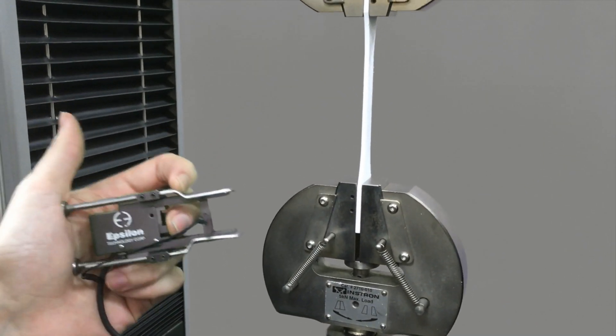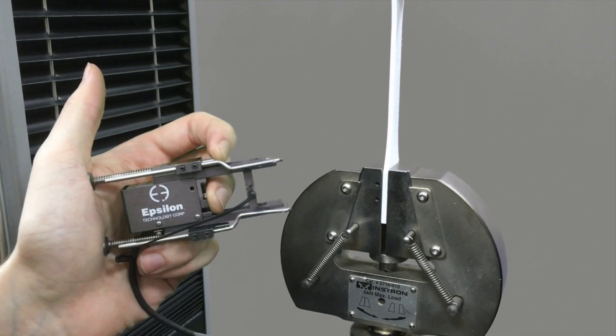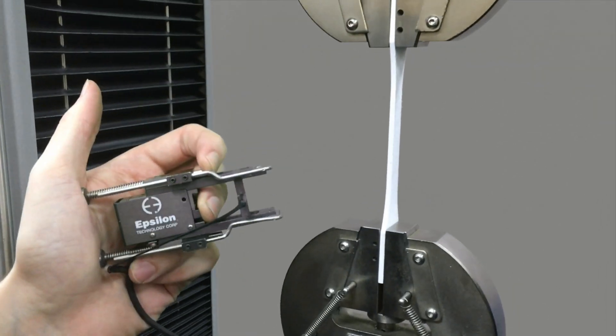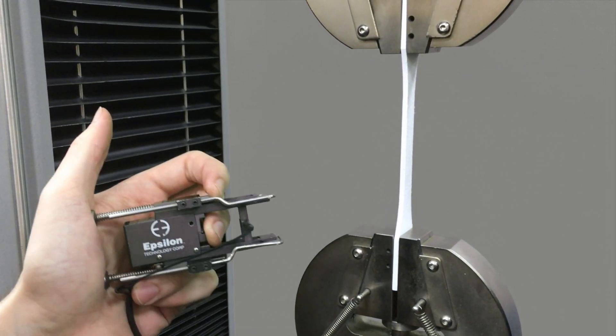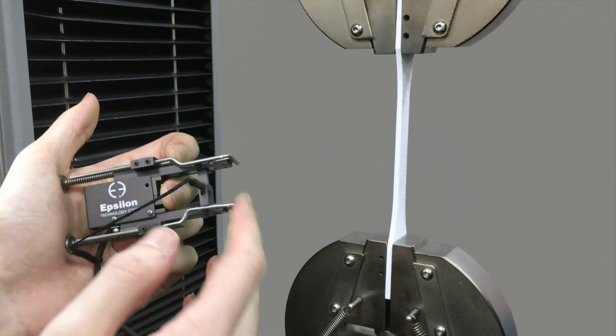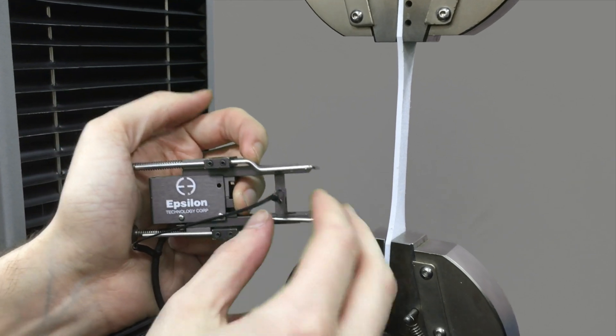The most important thing to remember about extensometers is that each one has what's called a gauge length. A gauge length is essentially a reference used for calculations in acquiring the data. When you set your extensometer on a sample, the teeth are a certain length apart to begin with. This is called the gauge length.